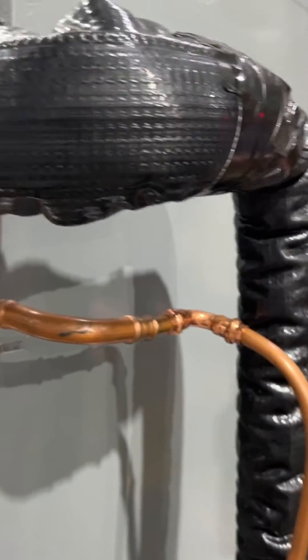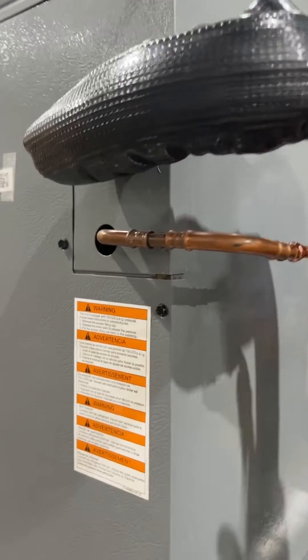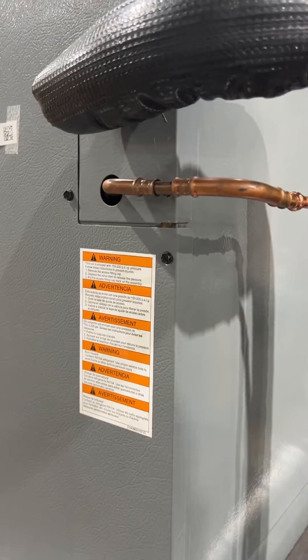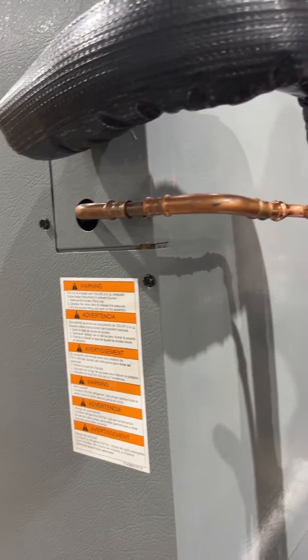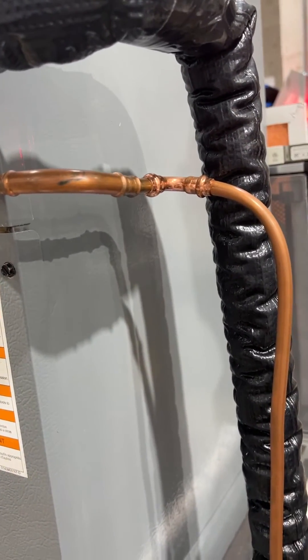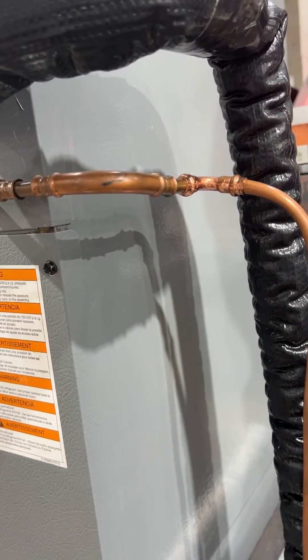So you got liquid and the suction. This is your liquid, and you notice we don't do any soldering anymore. We use the copper press fitting. We got rid of all the soldering because when you solder you get what they call flux inside the lines, and that gets into the TXV valves and into the compressors. When we put this in, that's the cleanest system you're going to get.